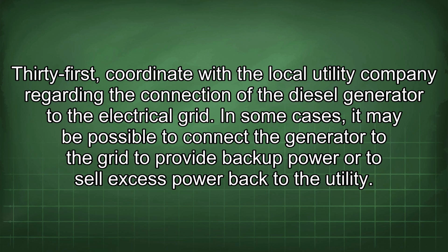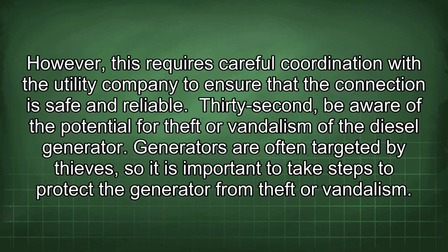31st. Coordinate with the local utility company regarding the connection of the diesel generator to the electrical grid. In some cases, it may be possible to connect the generator to the grid to provide backup power or to sell excess power back to the utility. However, this requires careful coordination with the utility company to ensure that the connection is safe and reliable.